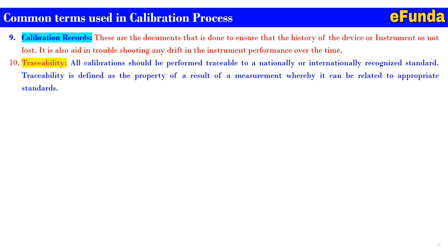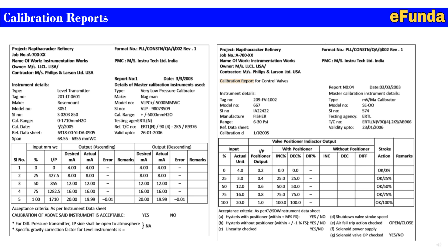Tenth is traceability: all calibrations should be performed traceable to a nationally or internationally recognized standard. Traceability is defined as the property of a measurement result whereby it can be related to an appropriate standard report. On screen, one can see on the left-hand side a calibration report for a level transmitter, and on the right-hand side a calibration report for a control valve. The level transmitter report includes instrument tag number, model number, and related details.